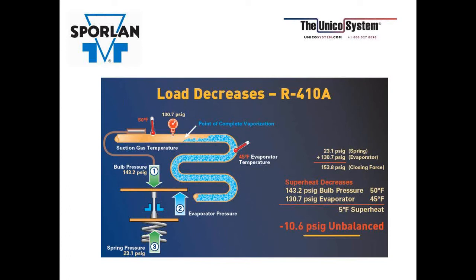Now if the point of vaporization, or the starve point, goes beyond the bulb location, you're going to have 0 degrees of superheat. And in that scenario, you don't know exactly where that point of vaporization is going to be. So you have a chance that you might be flooding back or slugging the compressor with liquid, because you don't know how far past that bulb, which is the control point, the liquid turns into a vapor.